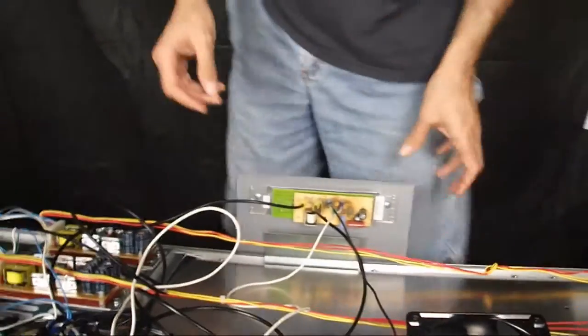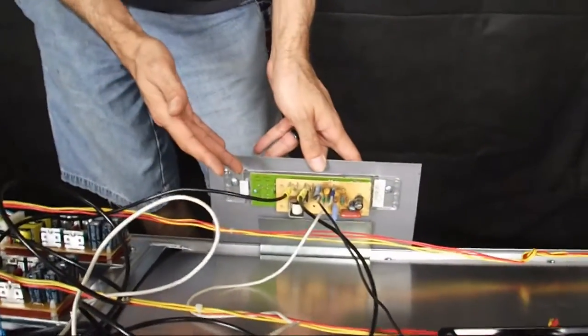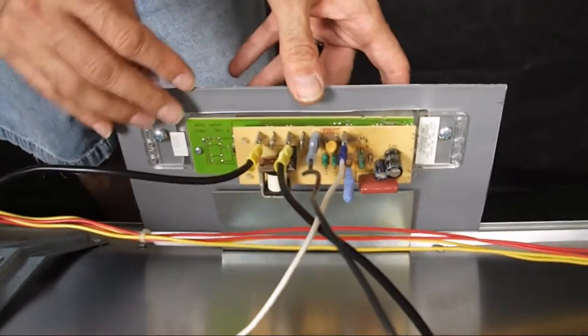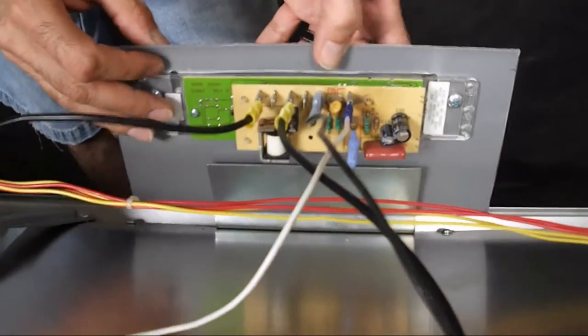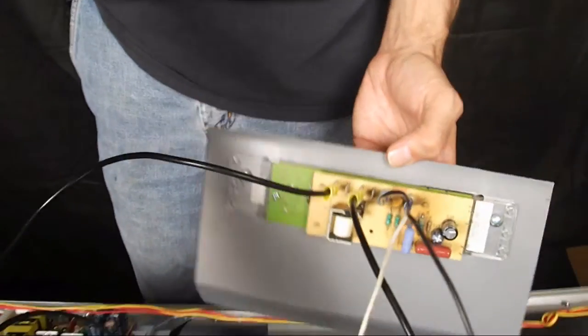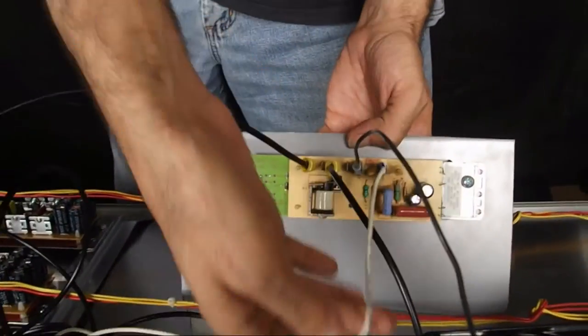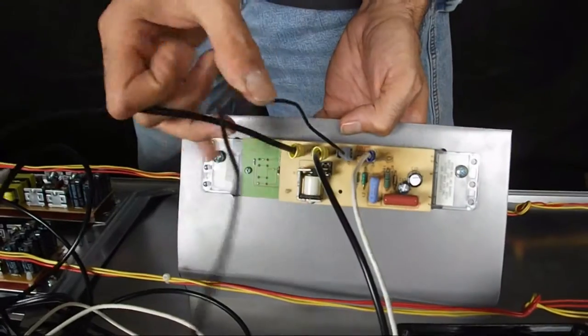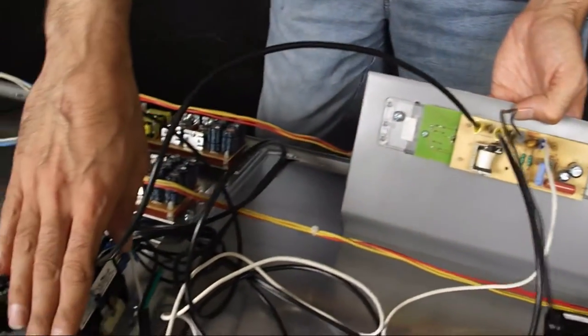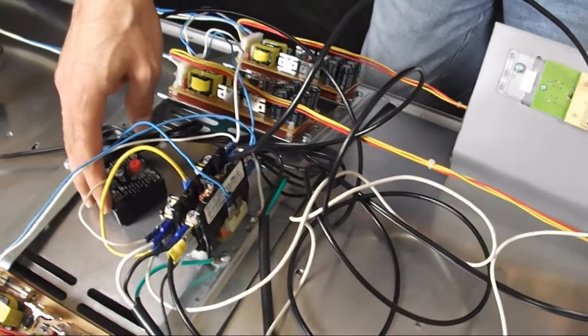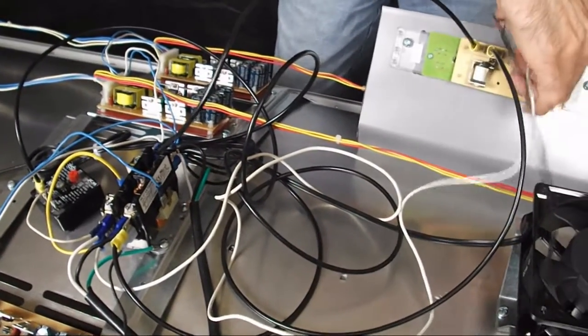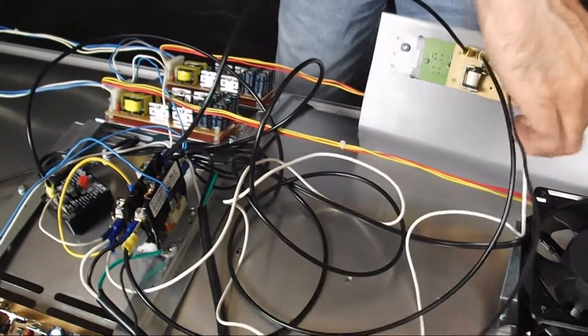So, when you go to replace this, it's the same instructions whether you're doing a 120 volt or a 240 volt Borg timer. But this is what it would look like when you start out. So, I'm going to take this up, and I'll show you the wiring configuration. Right now, we have a neutral coming in, and we have three black wires, and they go back here to the contactor and to the backup timer. What I'm going to do first is just make sure the bed is unplugged, and I'm going to disconnect the wires from the original timer.